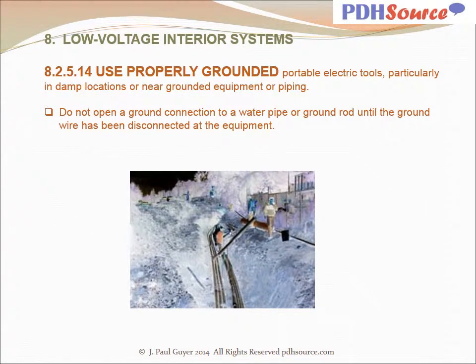Use properly grounded, portable electric tools, particularly in damp locations or near grounded equipment or piping. Do not open a ground connection to a water pipe or ground rod until the ground wire has been disconnected at the equipment.